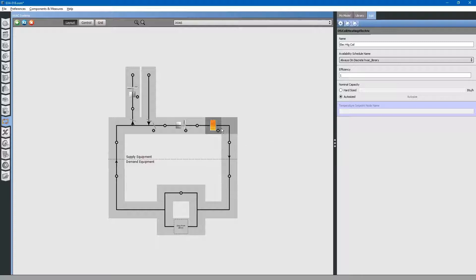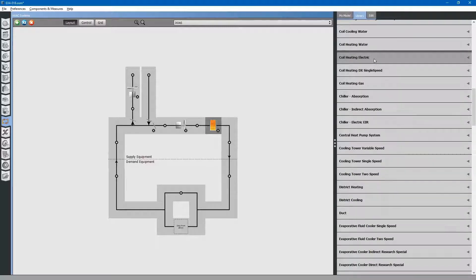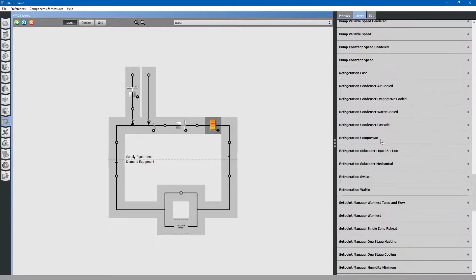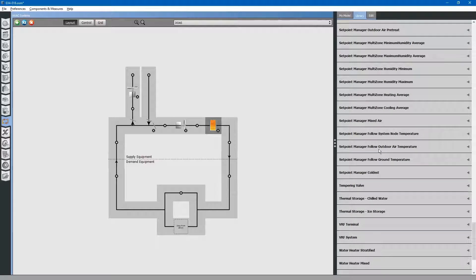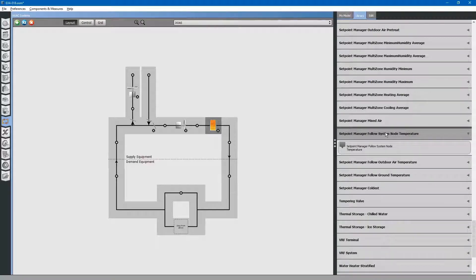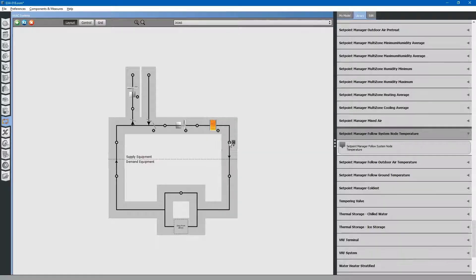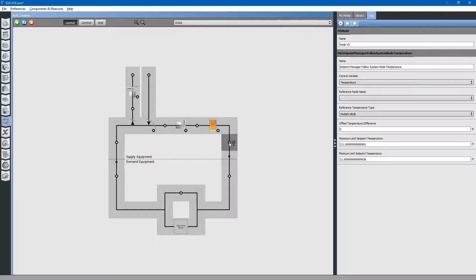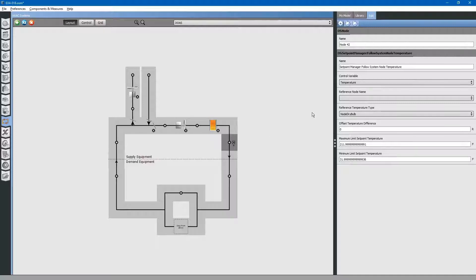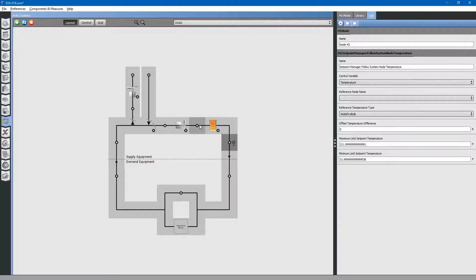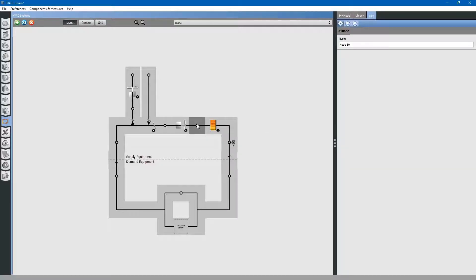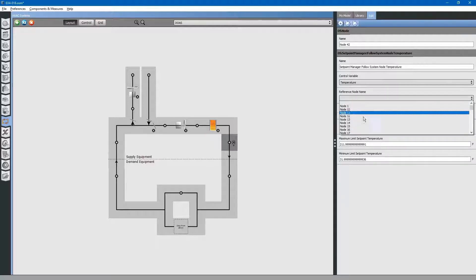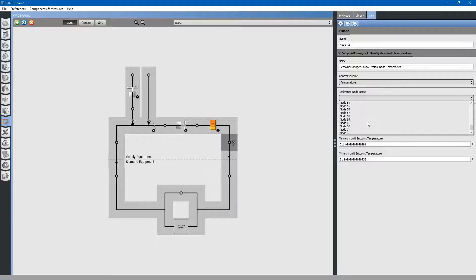Next, we need some way to control the electric heater. To do that, OpenStudio uses set point managers. Browse for set point manager. There are various different control strategies that you can use. We will select node temperature. Drag and drop to the node. Select it to edit its properties. We will be controlling temperature at this point in the ductwork. We need a reference node to see how much heat to input in order to maintain the set point. Our reference node will be right before the electric heater, this node right here, node 60. Drop down and select node 60 for the reference node name.